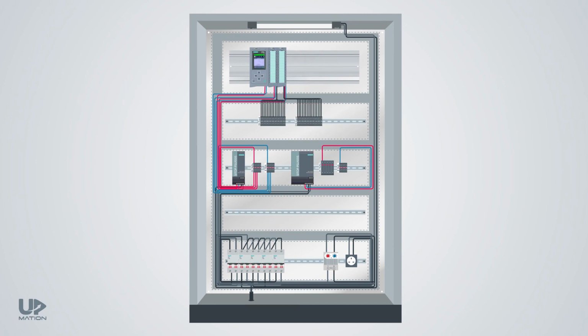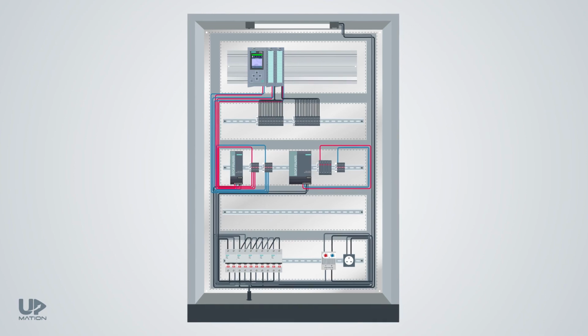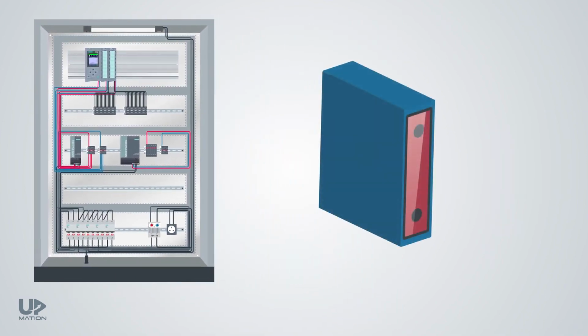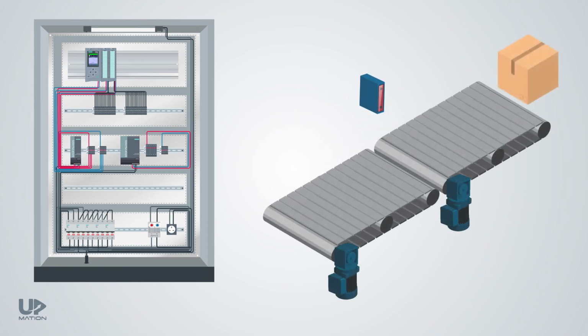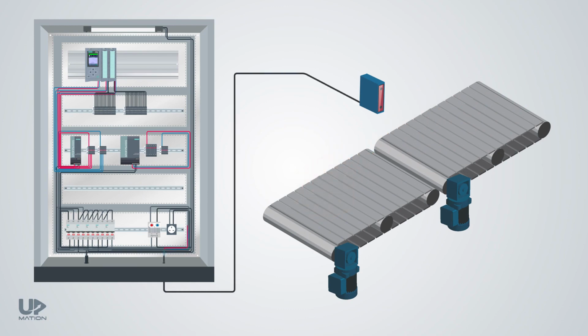Now, let's have a brief overview of how to connect the sensor to our control panel. Take this photoelectric sensor as an example that is installed adjacent to the conveyor and is supposed to recognize the boxes that are passing by on the conveyor. As this sensor requires power to operate, I'd connect the 24 volts to that from the second power supply's terminal box. It should return these 24 volts to the PLC input card in case it senses a box or object in front of that. So I'm gonna go ahead and connect a wire from the sensor to its corresponding PLC's input channel. After this sensor informs the PLC about the presence of the box, the PLC should command the next conveyor's three-phase motor to start turning.